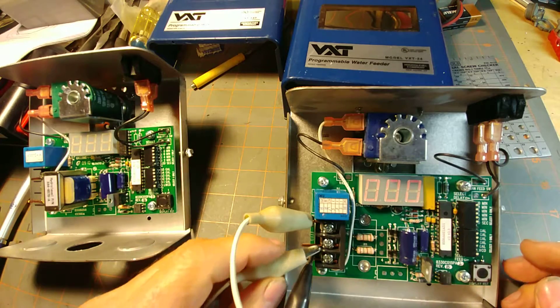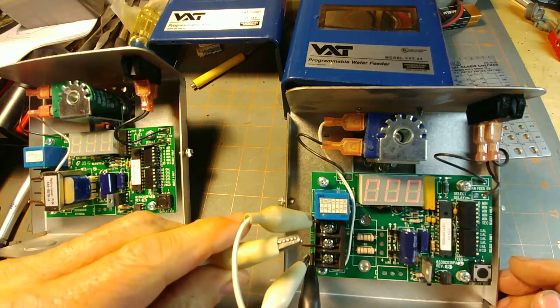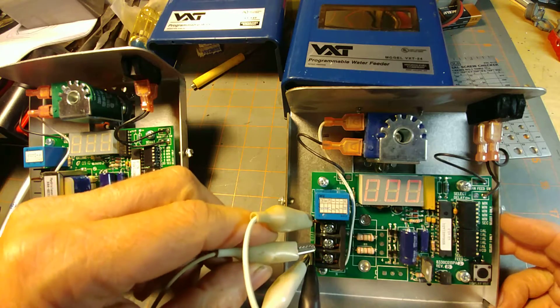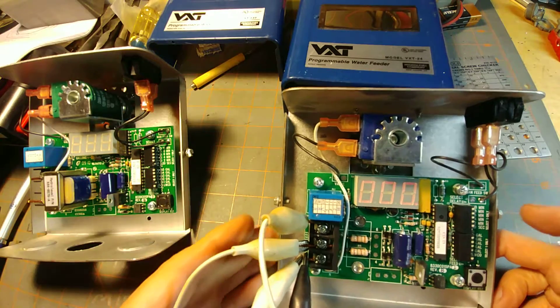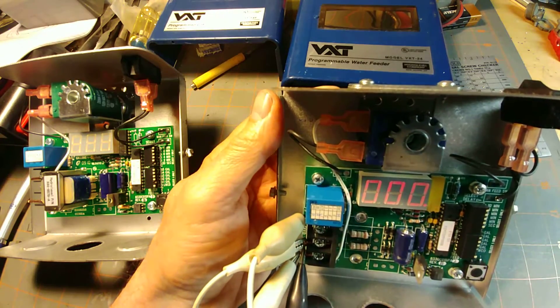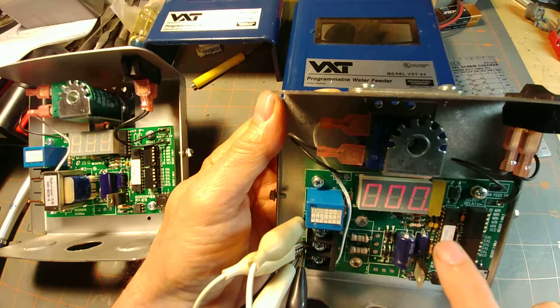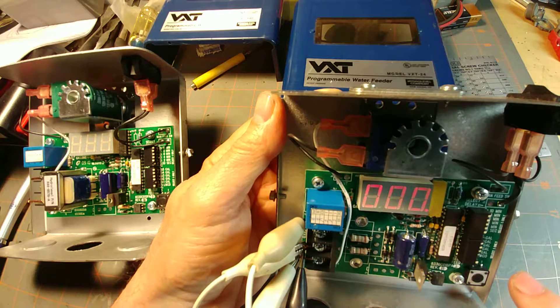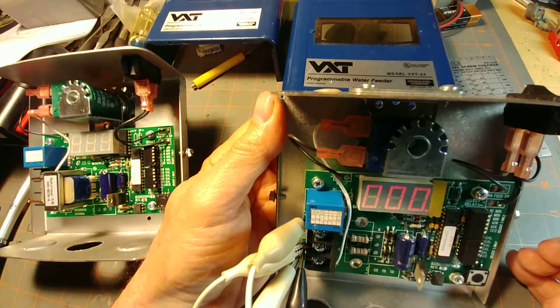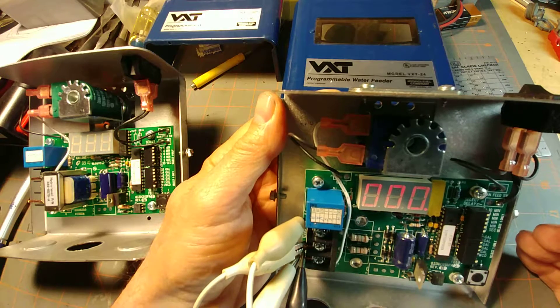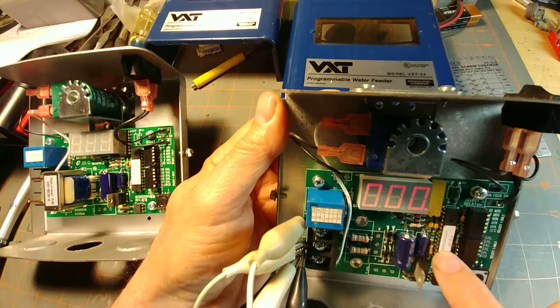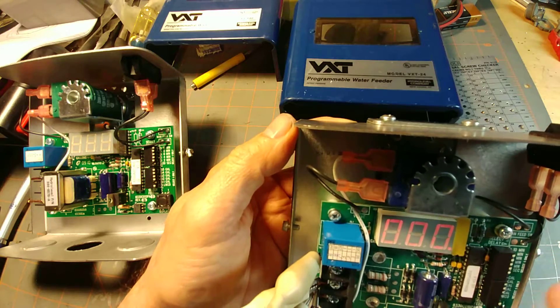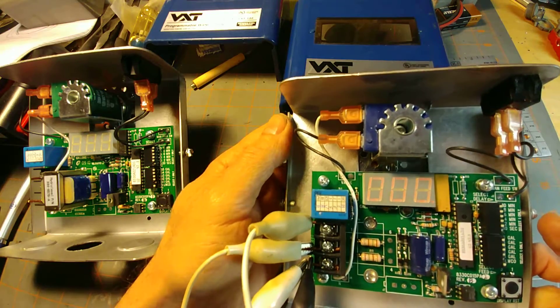I'm going to do that by simply jumpering the hot lead. You see now that there is a period after the zero. What that period means is that this microprocessor chip is getting the signal from the low water cutoff that the boiler needs water. If you set your delay here for 30 seconds, it should time out approximately 30 seconds. There's a quartz clock in here timing it out. Then at the end of 30 seconds, it's going to energize the coil, and you can hear the coil buzzing away.